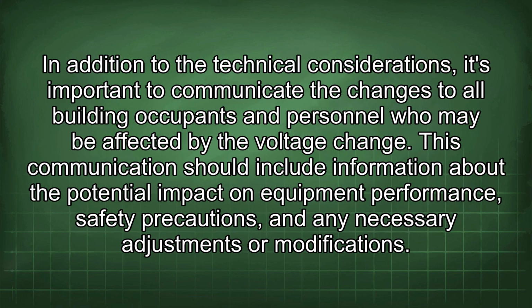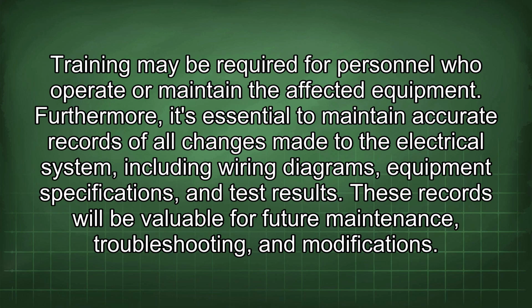In addition to the technical considerations, it's important to communicate the changes to all building occupants and personnel who may be affected by the voltage change. This communication should include information about the potential impact on equipment performance, safety precautions, and any necessary adjustments or modifications. Training may be required for personnel who operate or maintain the affected equipment. Furthermore, it's essential to maintain accurate records of all changes made to the electrical system, including wiring diagrams, equipment specifications, and test results. These records will be valuable for future maintenance, troubleshooting, and modifications.